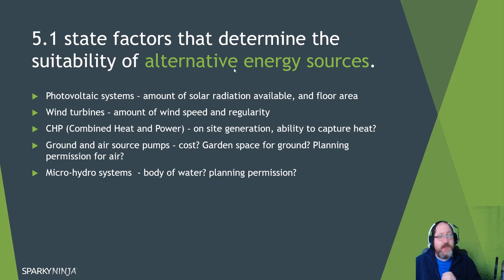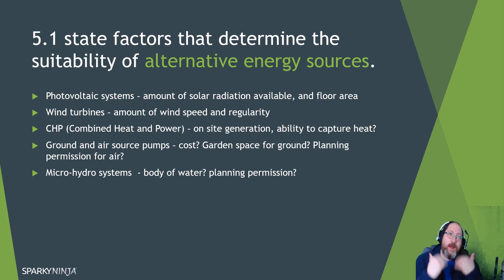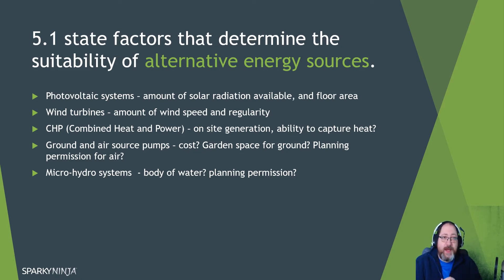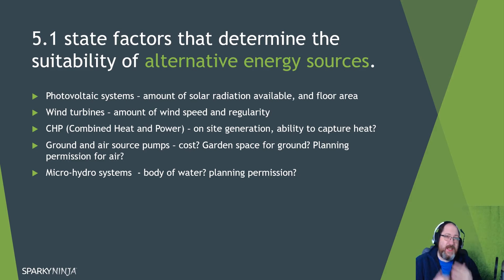For photovoltaics, how much solar radiation is available? In the northern hemisphere, you ideally want a south-facing angle. Have you got the space — is it just on the roof? There are calculations to quantify how much area achieves how much power, and whether it's a standby, backup, or temporary supply. For wind turbines, you need sufficient and regular wind speed — near the shore or coastline you'll often have constant wind, but on flatland with only occasional wind days, efficiency becomes a concern.